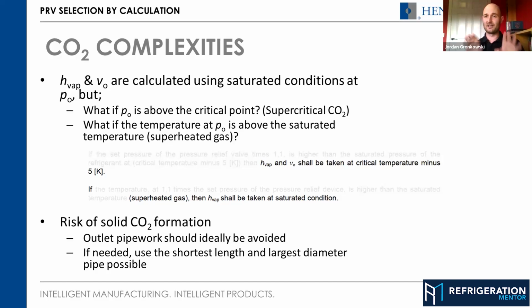So for an angled valve coming out, if all you want to do is point it upwards, then a simple angle that would point the flow up would be better than piping it through meters and meters of pipework to the roof, because that's when you'll get the solid CO2 forming, which is a blockage in the exit of the valve. Again, potentially very dangerous. Let's stick on that point, because here in Canada, this is why you need to know your code. Different provinces have different rules and regulations.